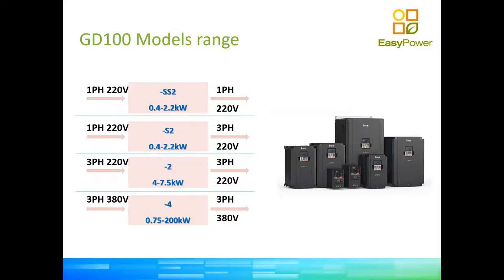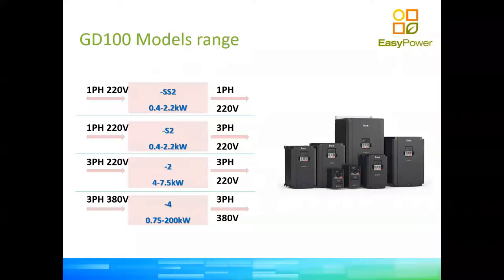As long as we have the correct information from you regarding your pump, depth, and voltage, we can quote you for exactly the right amount of VSDs. A common question is whether you can run two pumps with one pump inverter as long as it's big enough. The answer is: if the pumps are identical — identical motors, pumping at identical heads — they would have identical flows, so you could treat them as one big pump and run them simultaneously. However, you cannot run a booster pump and a borehole pump together, because the electrical parameters, speed, and power requirements are different. In that case you need separate pump inverters.